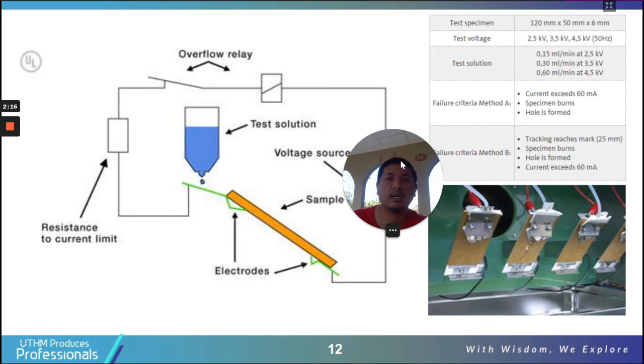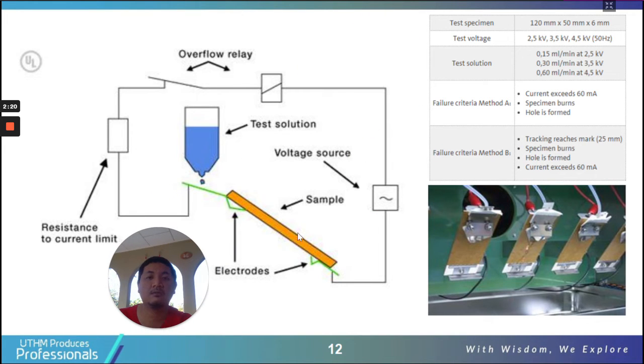All right, so we have another picture of the tracking test, much simpler. You can see here we have the supply, and then the supply is connected to the electrode, which is connected to the top of the sample, and then the bottom of the sample is connected to the ground. And of course we need to have the test solution, or the water that is being dropped on the surface of the insulation, the surface of the sample. And then we put the resistance to limit the current. That is basically the concept here.